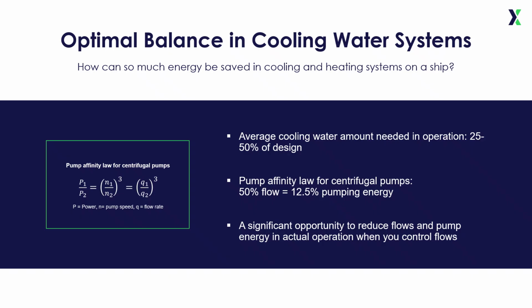So, how can so much energy really be saved in cooling and heating systems on a ship? The answer lies in maintaining the optimal flow balance in cooling water systems, thus ensuring that only the cooling water required is guided towards each consumer at all times. By aligning system performance with actual operating conditions, Frese FUELSAVE unlocks both energy savings and operational reliability, ensuring efficiency without compromises.